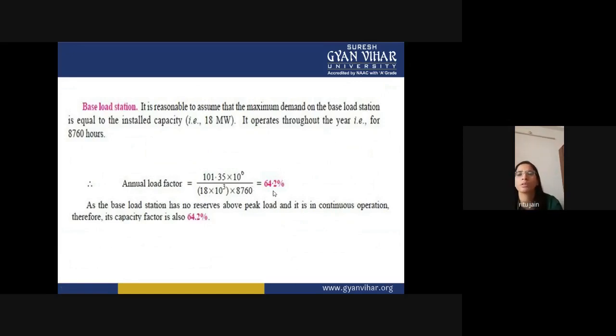As the base load station has no reserves above peak load and it is in continuous operation, therefore its capacity factor is also 64.2%, which is more than your standby unit, because the standby unit always comes into the picture when you require peak load, and base load is in continuous operation. That's why its capacity factor is higher than your peak load or standby unit.